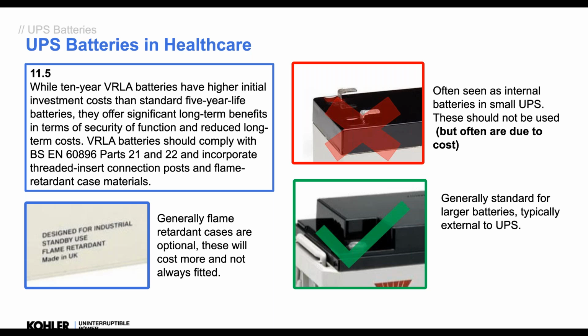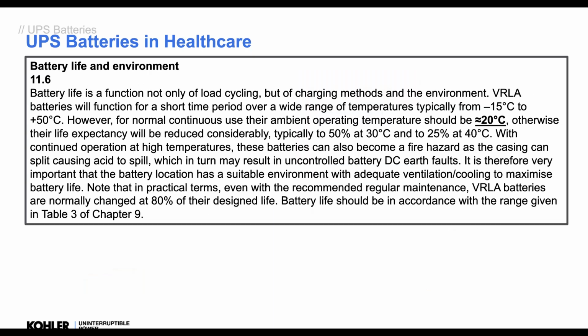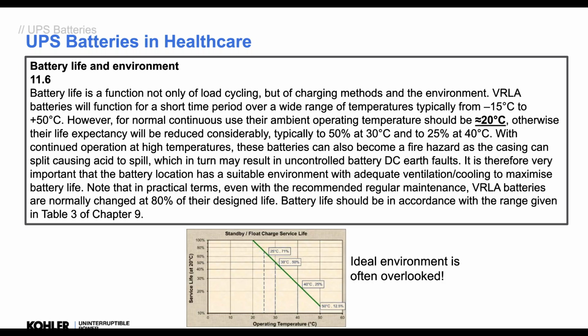And you need to be careful with this, because if you just go to a UPS manufacturer and say, I want a 20 kilowatt UPS for an hour, you might not necessarily get what you want, okay? You've got to say exactly what you need from the UPS and the battery. Now, one thing that HTM is quite clear on, you should keep the battery at 20 degrees, okay? It makes sure the battery performs correctly. We size the battery at a temperature, okay, typically 20 degrees, and that's for the autonomy. Because if it's below 20 degrees, it won't do the autonomy. Above 20 degrees, yes, it will do the autonomy well, but the lifespan of that battery will be severely reduced, okay? So very important to condition the battery correctly for lots of reasons, all right?